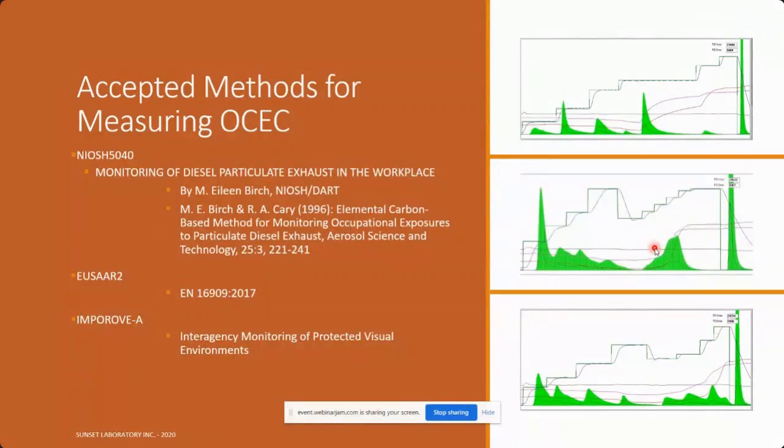And the IMPROVE method, instead of using a fixed time to proceed to the next temperature step, uses a function where we wait for the detector to return to baseline. This results in an unknown time limit, as we might say, for the length of time that this analysis takes, because every sample is slightly different.